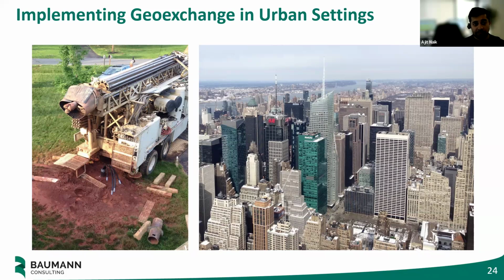Successful strategies typically involve designs with low thermal resistance boreholes and low pressure drop circuits, so you don't have to pump too hard to push water through the borehole. When the water is in the borehole, it's able to pull a lot of heat out of the ground or reject a lot of heat back into the ground. Being thermally conductive, not very resistant, and easy to move water through—those are really key for boreholes anywhere, but especially in urban settings.